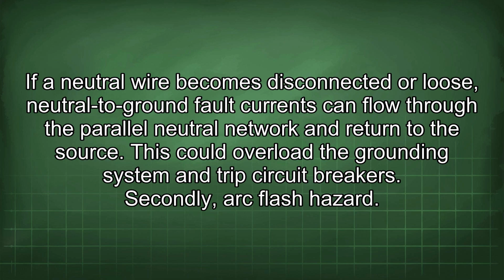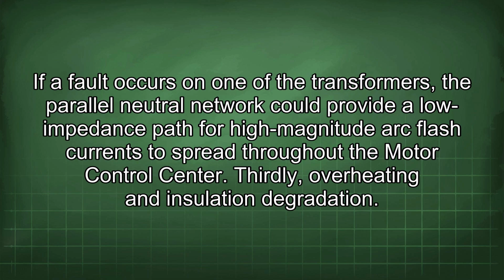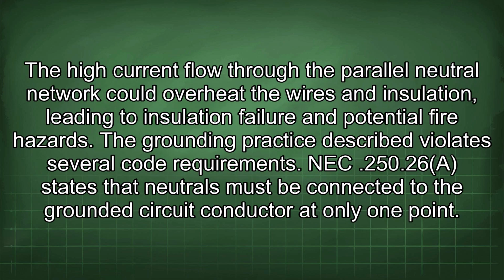Secondly, arc flash hazard. If a fault occurs on one of the transformers, the parallel neutral network could provide a low impedance path for high magnitude arc flash currents to spread throughout the motor control center. Thirdly, overheating and insulation degradation. The high current flow through the parallel neutral network could overheat the wires and insulation, leading to insulation failure and potential fire hazards. The grounding practice described violates several code requirements.